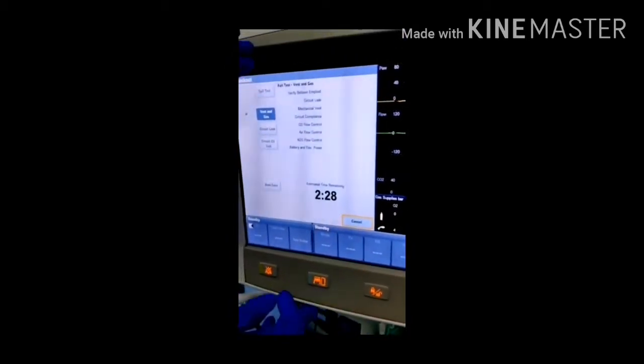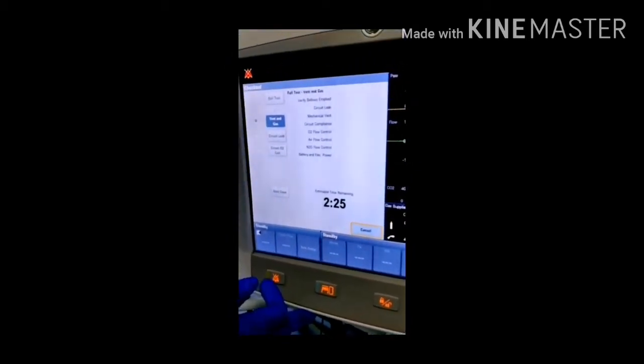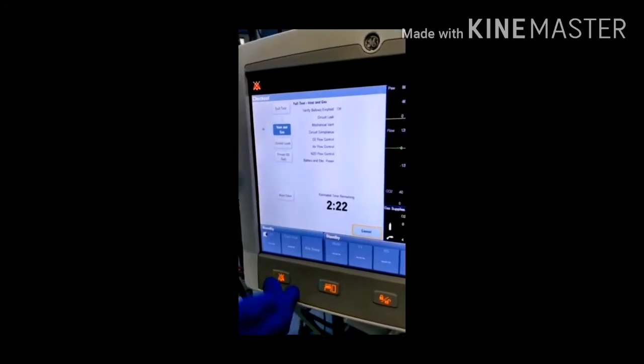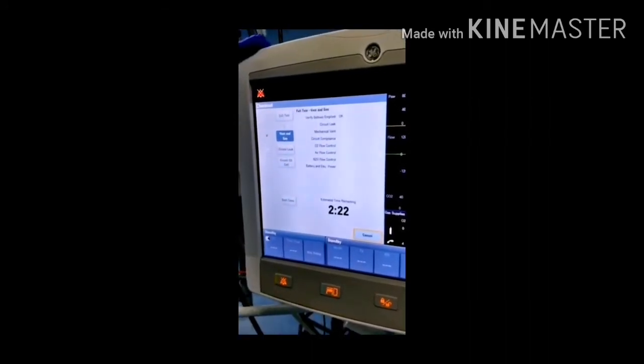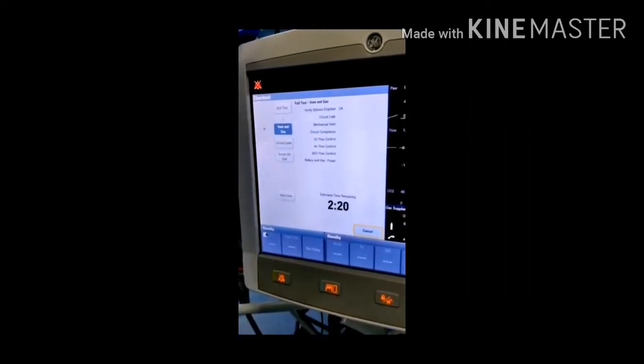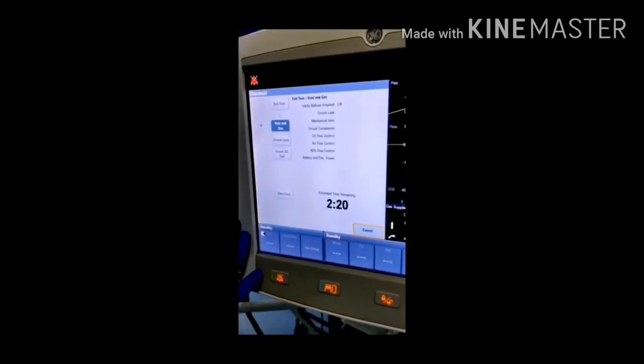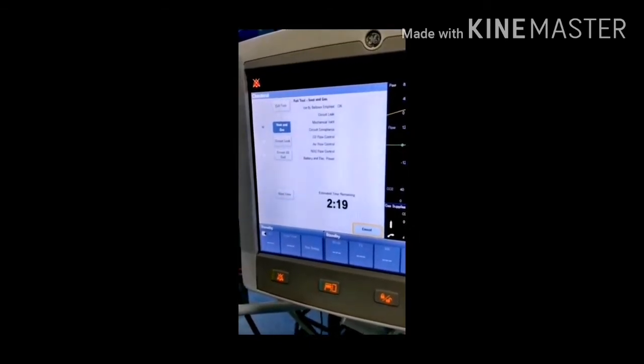Now we have to occlude the patient Y. To occlude it, we can just connect it over here so that it stays occluded, or else you can occlude it with your hands itself, but press tightly and you can continue it. So here you will get to know the leakages in the circuit, in the mechanical vent, the compliance, how much it provides for the leakage, and all the gases, flow control and battery of the system. It will take about 2.5 minutes.